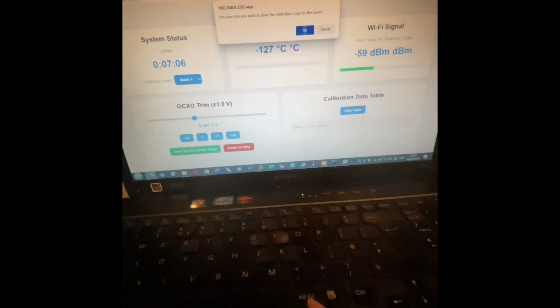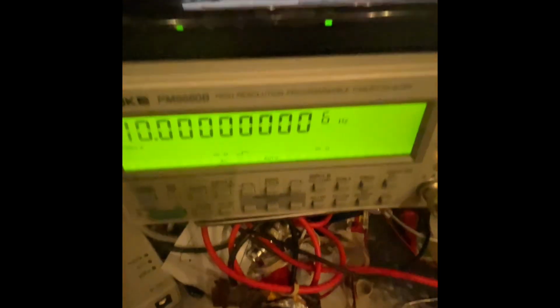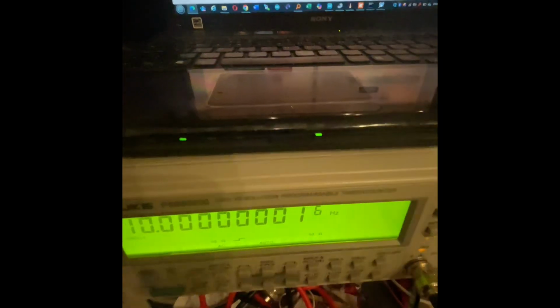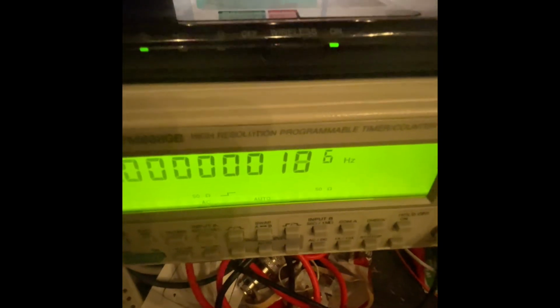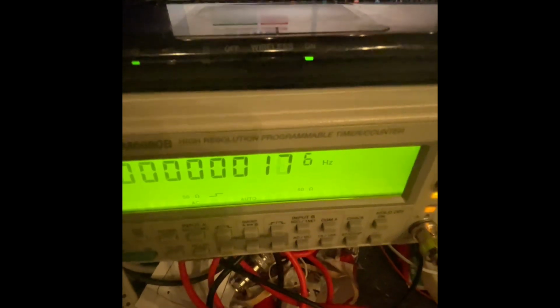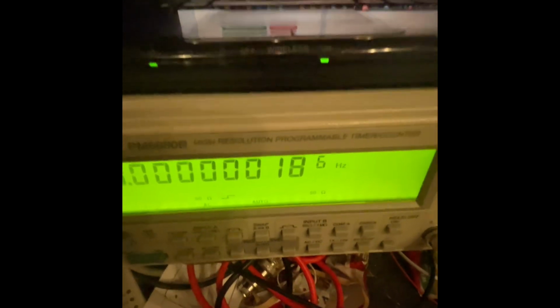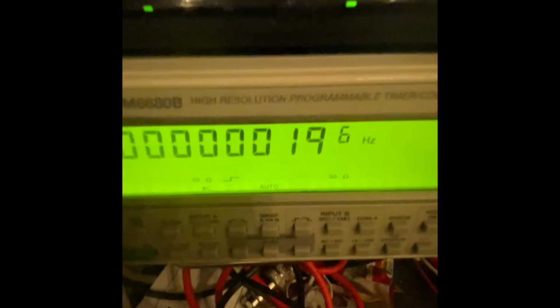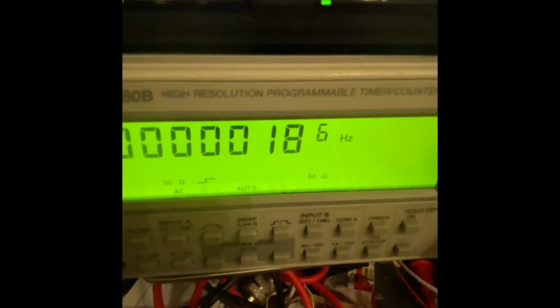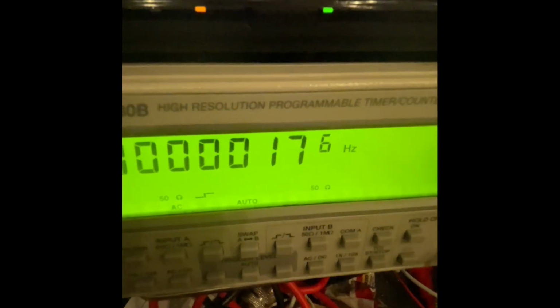But if I remove the calibration data, if we go here and I go reset calibration map, okay, are you sure you want to clear calibration? Yeah, let's do that. The calibration's off, and in a second now this will change because we know we're well off. So let's quickly hit a 1 or something. There we go, well off. All over the place. And that's not going to correct itself because I've just deleted the calibration table. So that's just going to sit there well off for the time being, and that is not going to sort itself out.